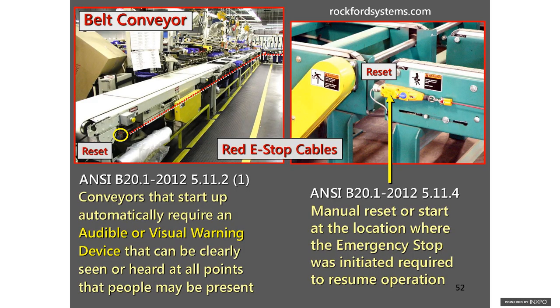As far as grab wire e-stop cables, emergency stop, this gives you an emergency stop capability for the entire length of the cable, which could be up to a couple of hundred feet, and may allow you to not need individual red emergency stop buttons spaced at a certain distance apart.